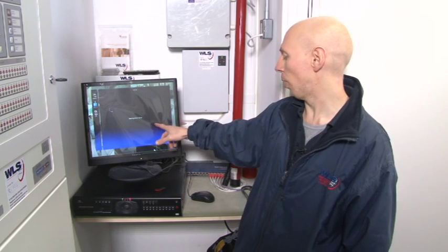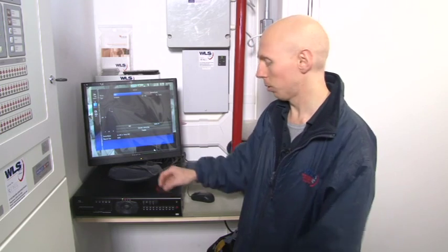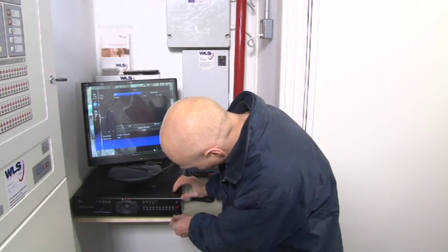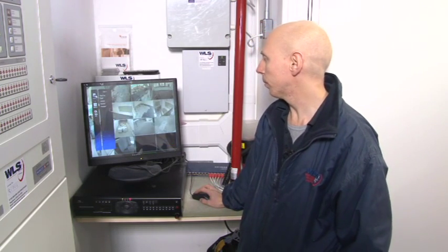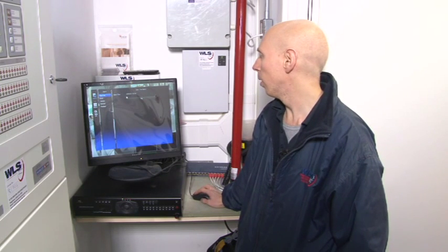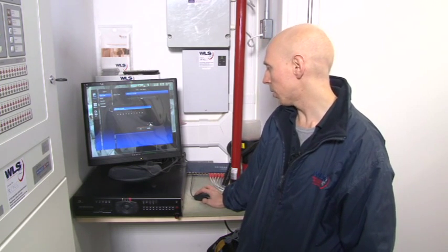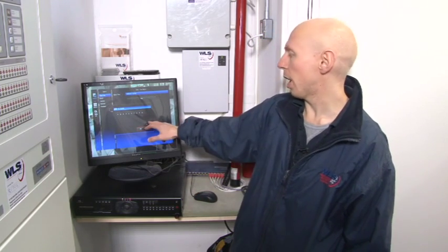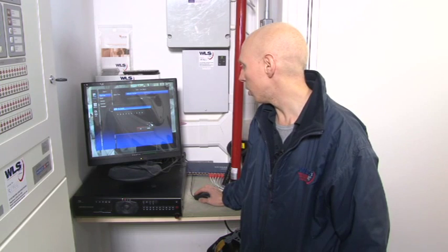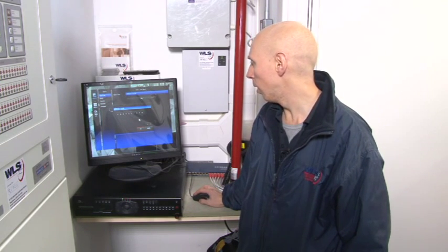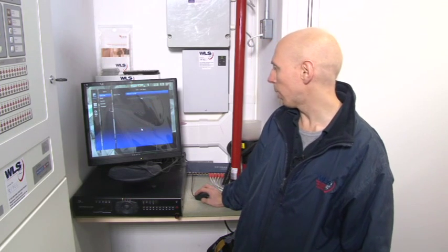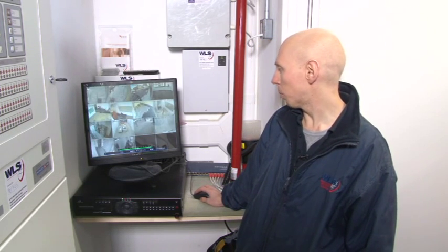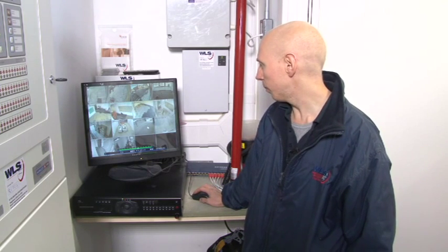At the moment it's searching for an archive device, because I don't have one plugged in, which I'm going to do now. USB into that. And what you can do is go to search, then dates and time. I'm going to go back to yesterday when I was using the system. So if you use the arrow keys to move across the date, I'm going to change it back to yesterday's date, the 24th, and set the time to 10:34 and 20 seconds, and push OK. And when I push play, that'll go back to then.